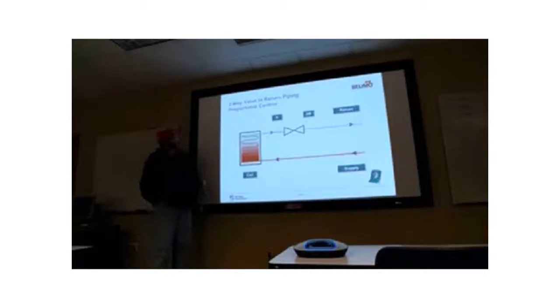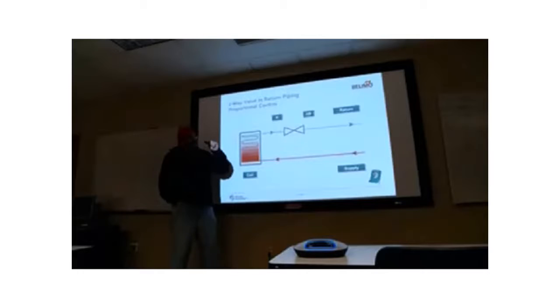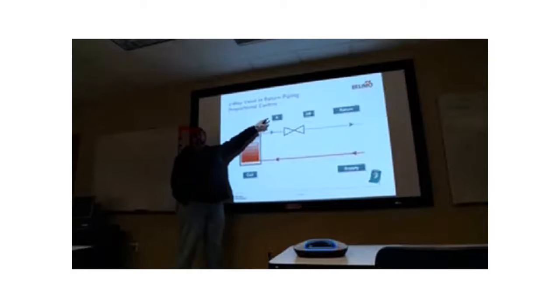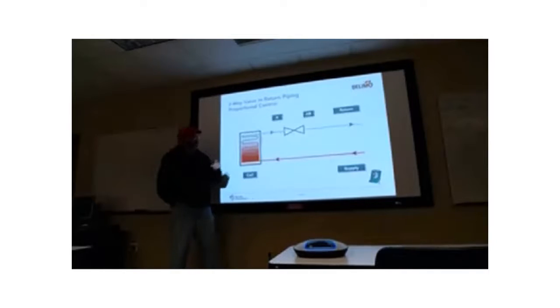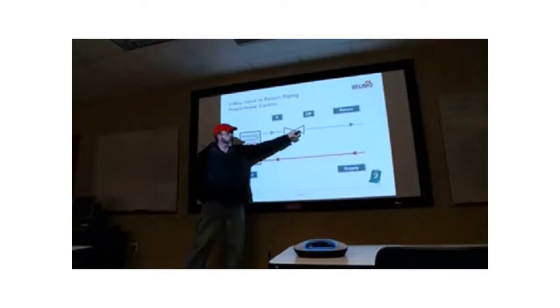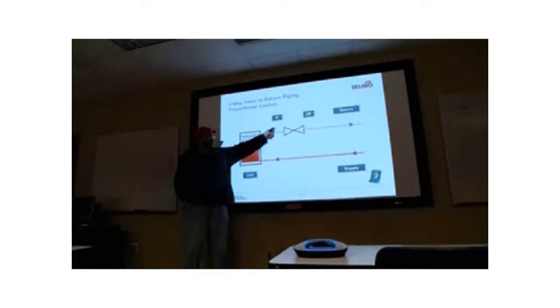Now, one thing that I'm going to probably beat my shoe on the table on throughout this presentation, at least for the next couple hours, is that you know what's going on here. And this, for our characterized control valves, it's going to be really important. This A port that's on all of our valves, it's called the A port. That's what they call the control port. Now, on a two-way valve, there's only two ports, right? This is the control port, and this is the common port. Now, why do you think I call this the control port?